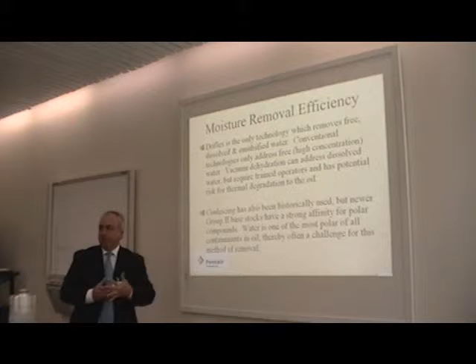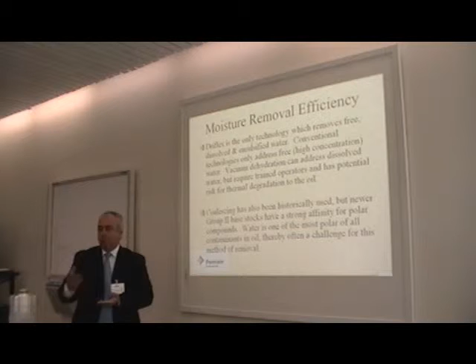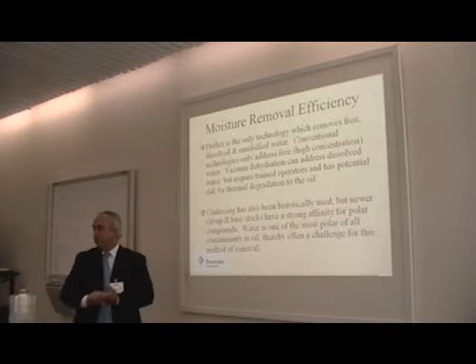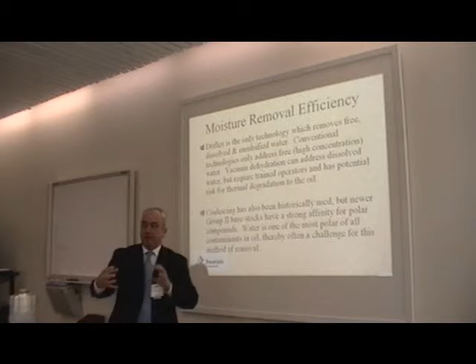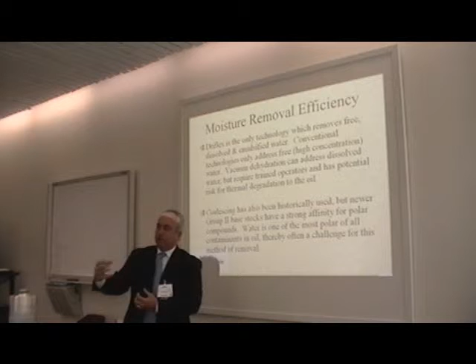Essentially, with this technology, it's one of the few capable of removing free, emulsified, as well as all of the dissolved moisture. We're seeing systems in transformers getting down to 5 parts per million water, incredibly dry systems. At the same time, we've designed hardware that eliminates all the operator interfaces of a vacuum purifier, so you can get the dryness of those technologies without all the operator requirements.